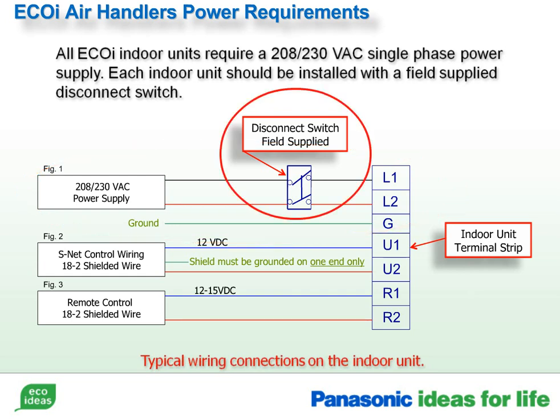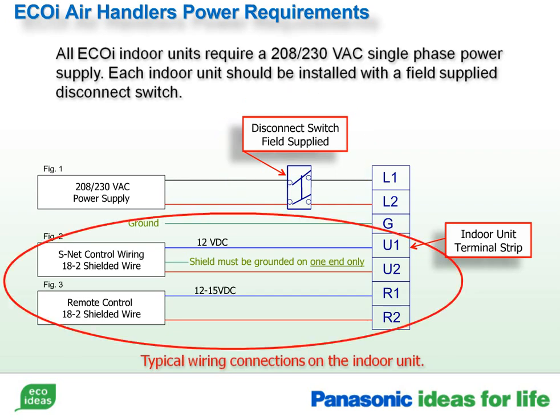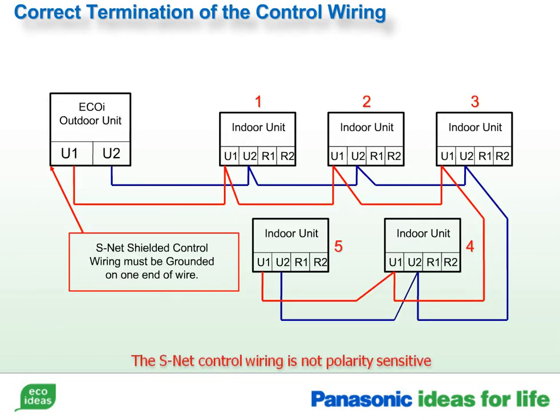Disconnects are not a Panasonic requirement, but are usually required by local codes. 18-gauge, 2-wire stranded shielded cable is required for all control wiring. The shielding of the wire should only be grounded at one end, which is typically connected at the outdoor. There are 2 acceptable methods of running the control wiring. The daisy chain method shown is the recommended configuration.